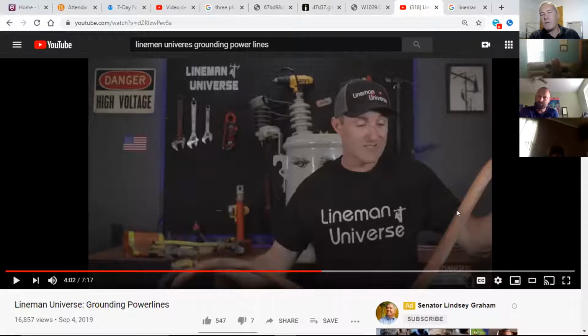A mechanical jumper is meant to bypass the flow of electricity. This cable has extra insulation on the outside and is rated for the amount of amps that are supposed to go through it. So if you have a circuit rated for 900 amps, you better use a 900 amp mechanical jumper.